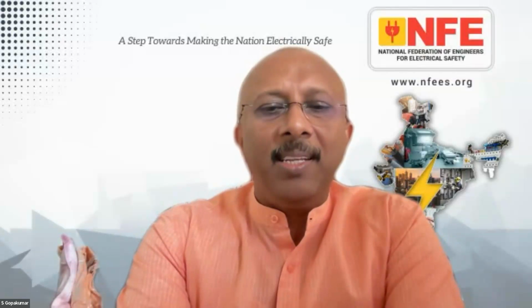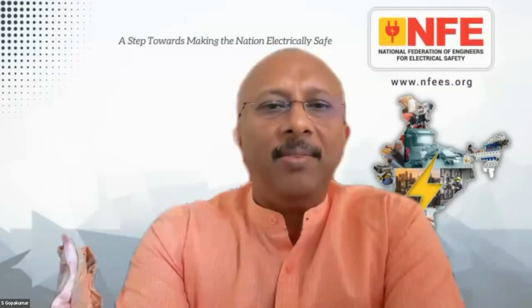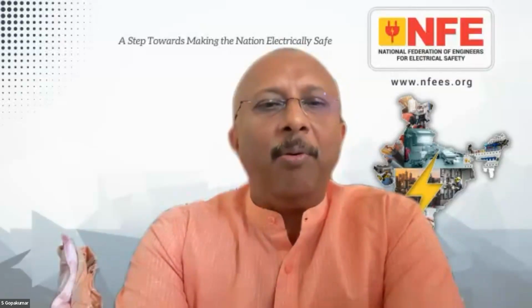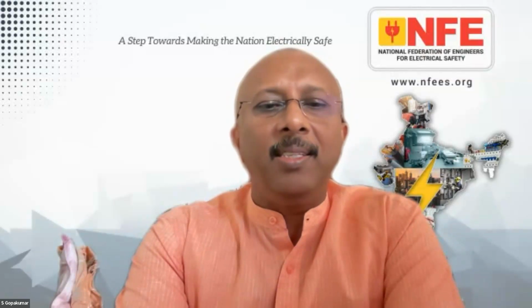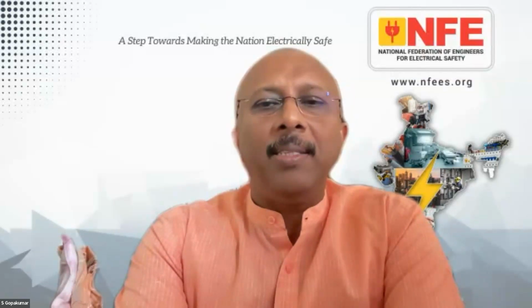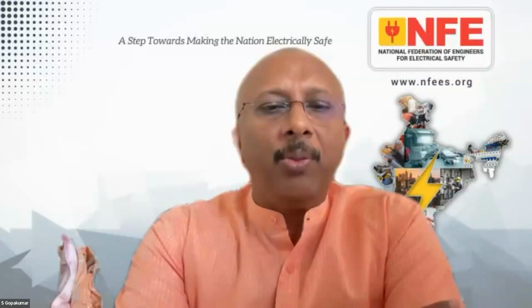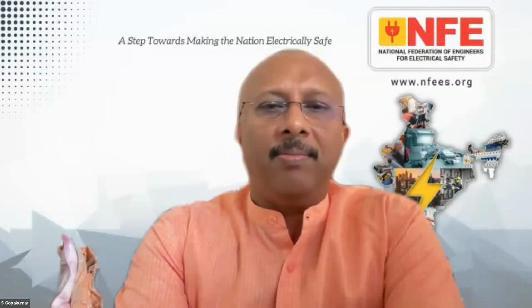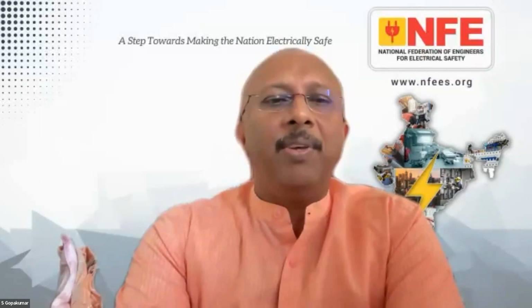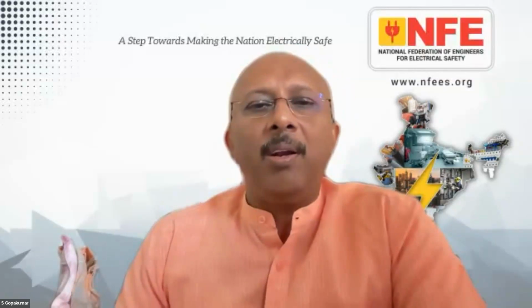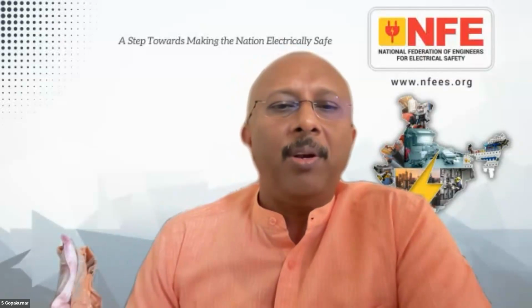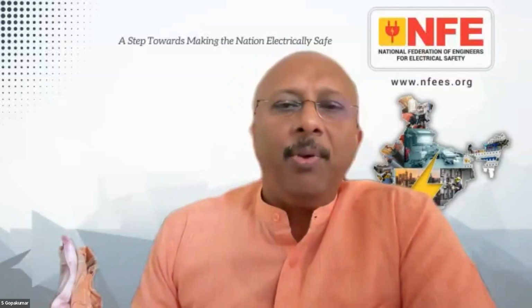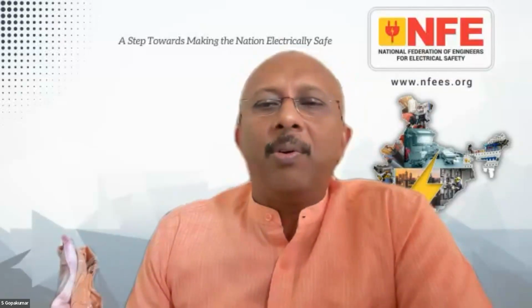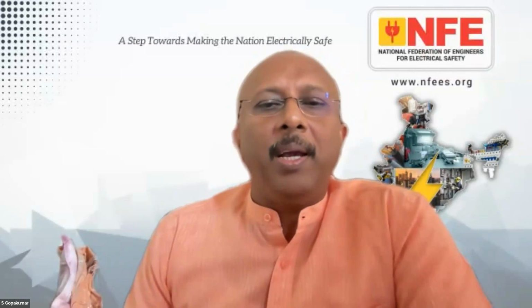Actually, this subject is not something we can answer simply. It's a complicated subject. If we look at a TT system, the neutral to earth voltage is because of the neutral current. So if you have single phase or unbalanced load, there is a neutral current flow, and the voltage drop is equivalent to this particular voltage. And if you have a TT system, of course, the neutral to earth potential will be high.